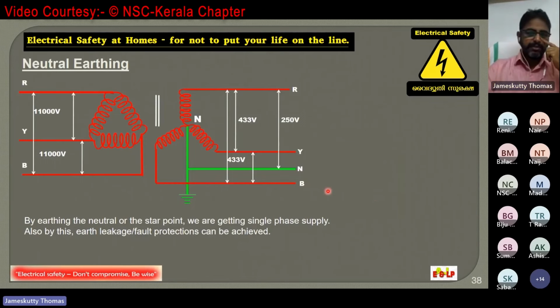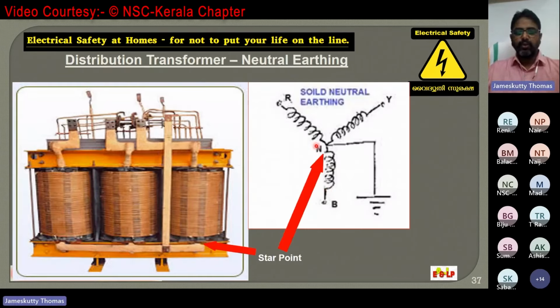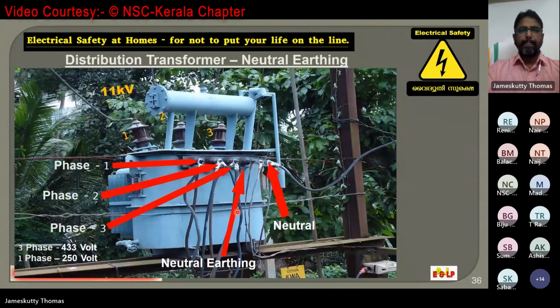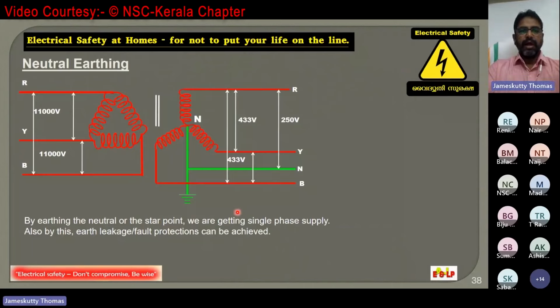Here in this diagram, you can see the neutral point, neutral and neutral earthing. So actually, what is the benefit of creating this neutral, and what for? If the star point is effectively earthed, the potential of the neutral will be 0 volts. So we may not get an electric shock in normal cases if we touch this neutral conductor, since we are standing on earth or ground, and the touching point and the foot are at the same potential. But if you touch the phase conductor, what will happen? We are touching the full voltage and we are standing on earth, so it is dangerous. That is why we call this phase wire the live conductor, which means dangerous, but the neutral is not live.